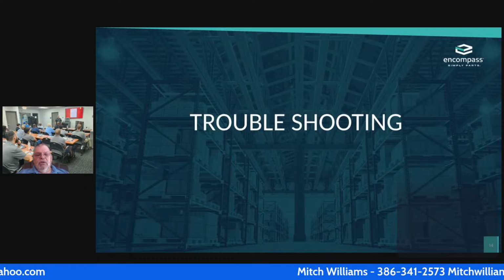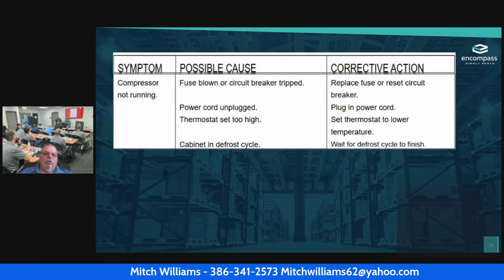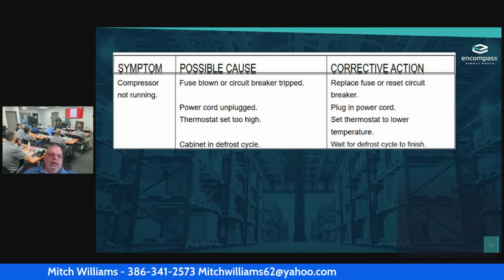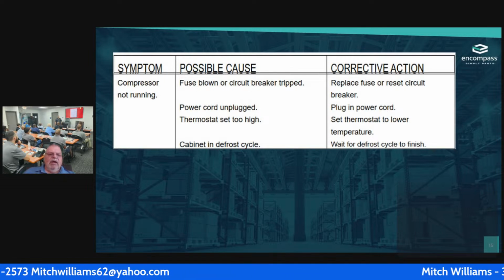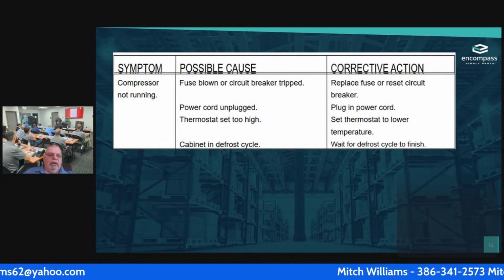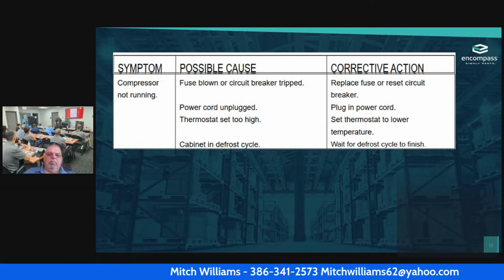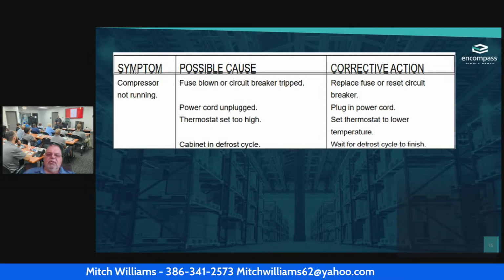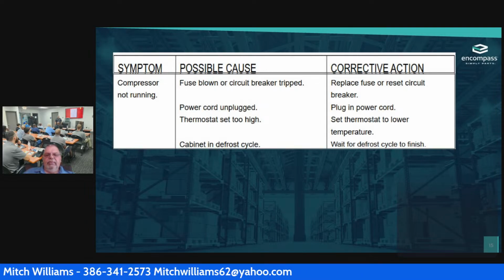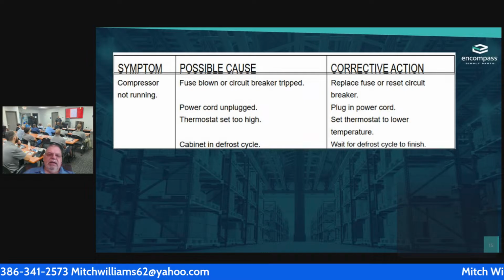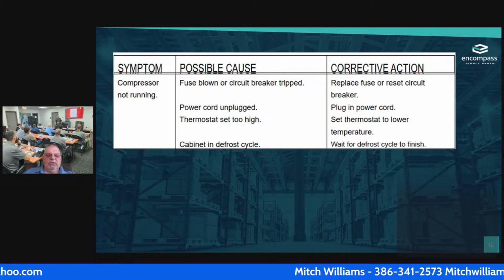Okay. So troubleshooting. So let's go by and we're going to start and go through this. If I come in and the compressor's not running, of course, the first thing I'm going to do is look for a blown fuse or the circuit breaker being tripped. Okay. I don't know many people that I find have a blown fuse anymore. It's usually the circuit breaker that's tripped.